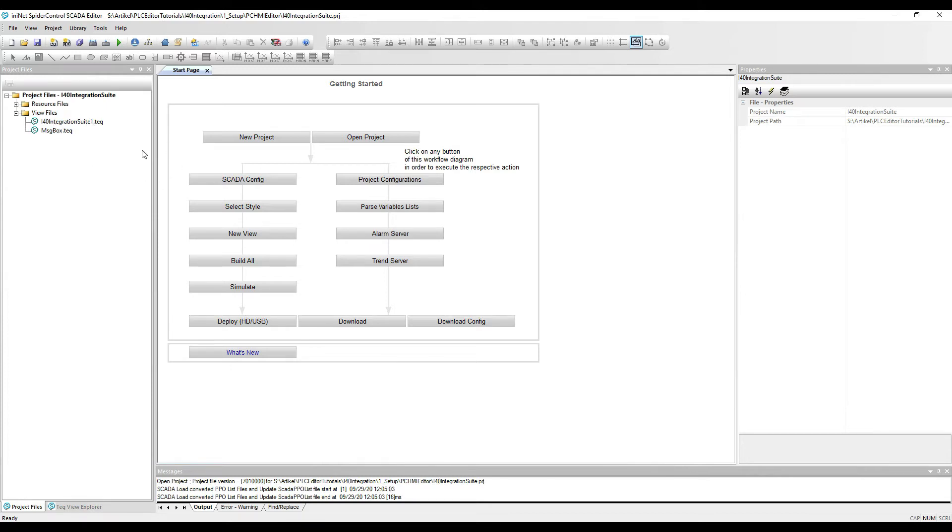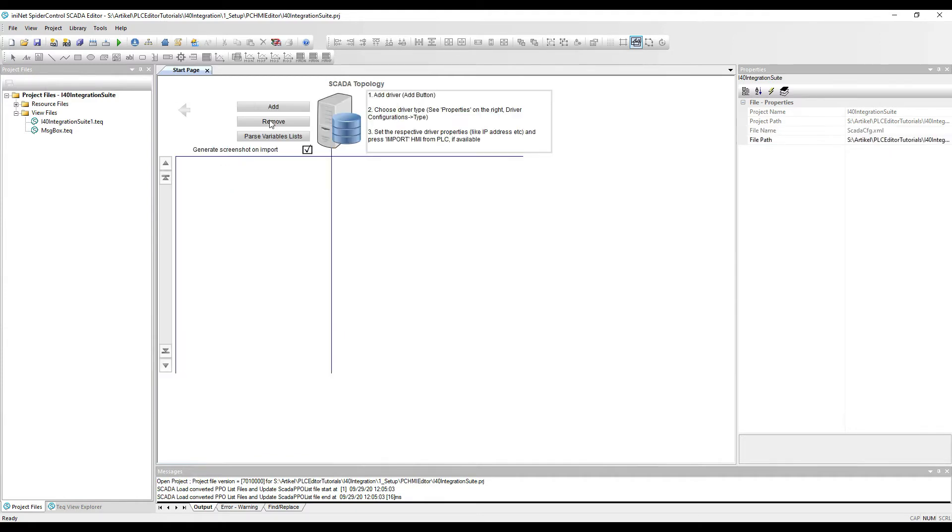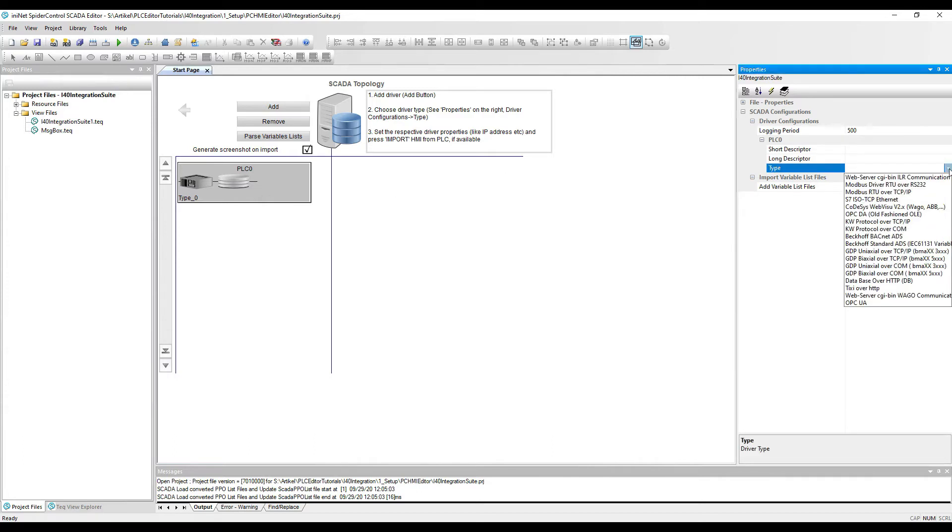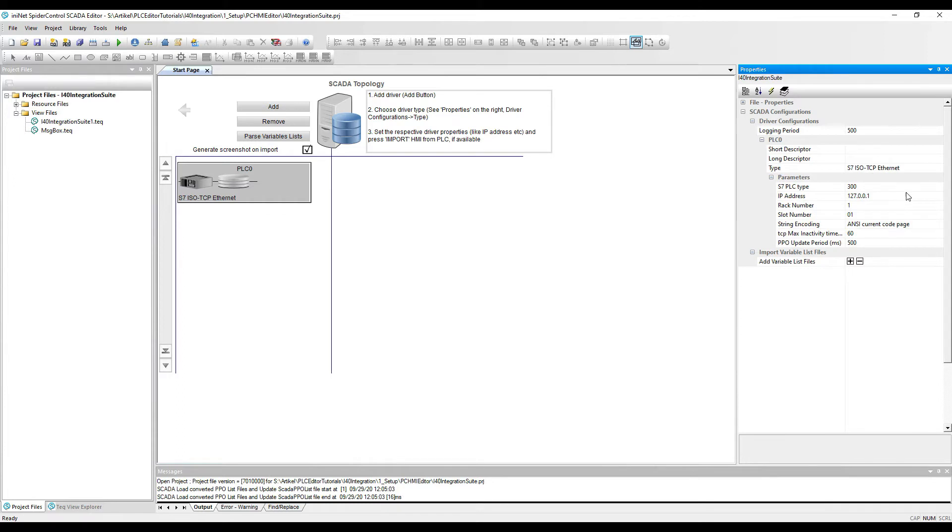First thing we have to do now is to go to the SCADA configuration and we will add the first driver. So the first PLC that we want to connect will be a SIMATIC S7-1200. To connect this, we will choose the S7-ISO-TCP protocol.